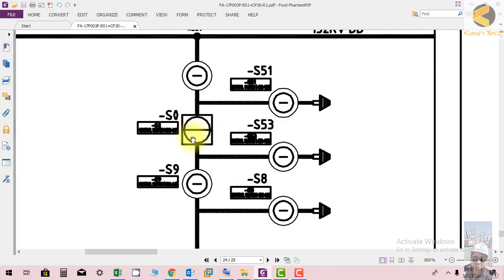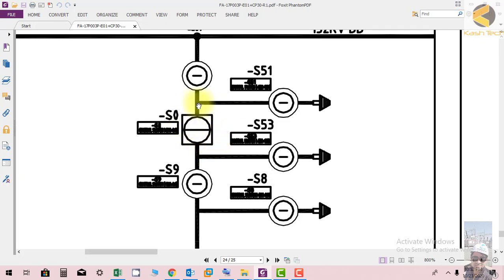It is called a discrepancy switch because it shows the discrepancy between the position of the switch and the actual status of the breaker. For example, this is the discrepancy switch for the circuit breaker, currently shown at off position. When the switch line is parallel with the bay line the breaker is considered closed; when perpendicular it is considered open. If the breaker is also in open position, there will be no light in the background of the switch.